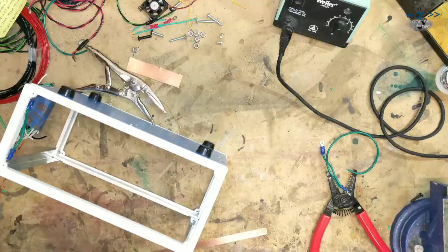But I mentioned the first reason for doing it was fault current. The second reason is for EMI, RFI blocking. There's not really any large switch mode power supplies in here, but in spite of that, a large rectifier diode operating under heavy current can actually generate a lot of ringing up into high frequency ranges. The filter on our plug will help keep some of that from going back out into the mains, but there is also some potential to radiate out of the chassis if it's not fully shielded.